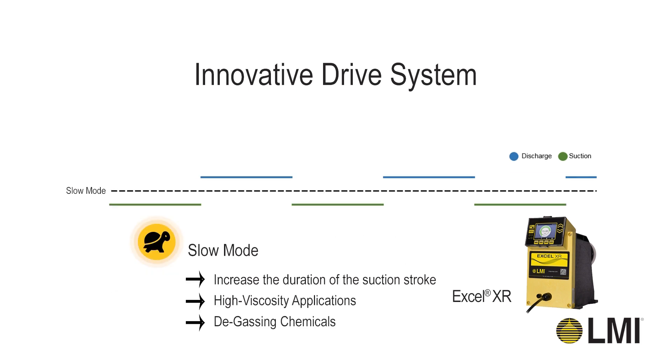In applications where chemicals are sensitive to suction stroke speed, the Excel XR Pump can engage in slow mode, which will slow down the suction stroke of the pump. This is a big advantage in applications that utilize high-viscosity chemicals or degassing chemicals such as peracetic acid.